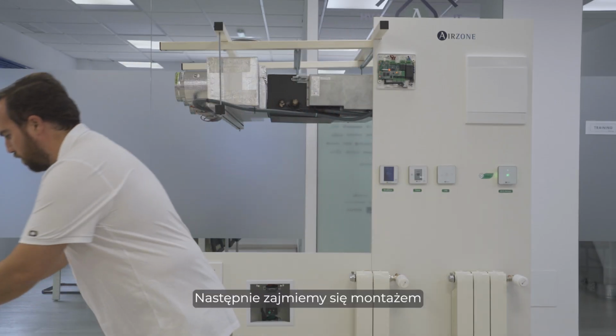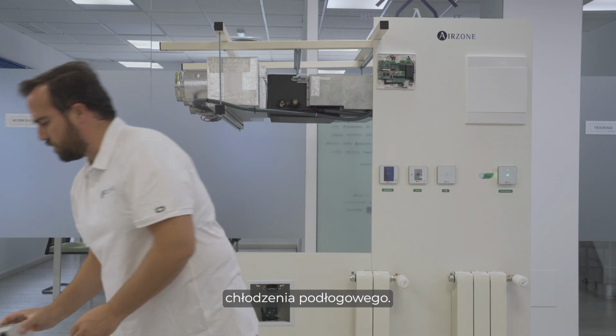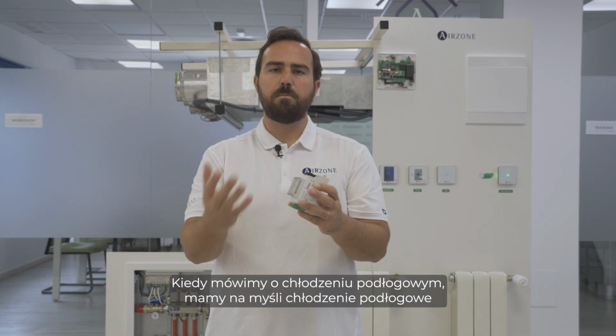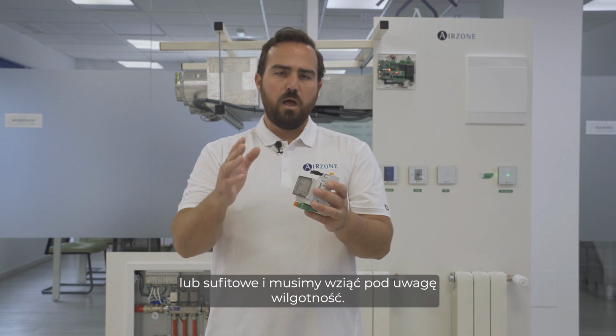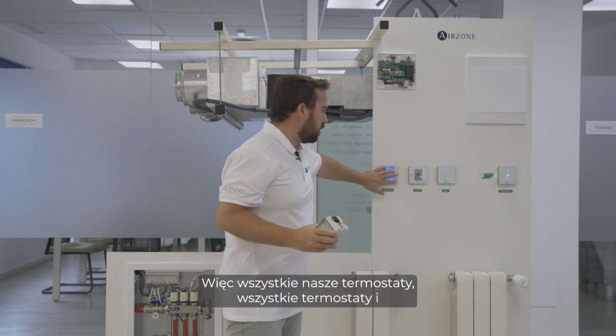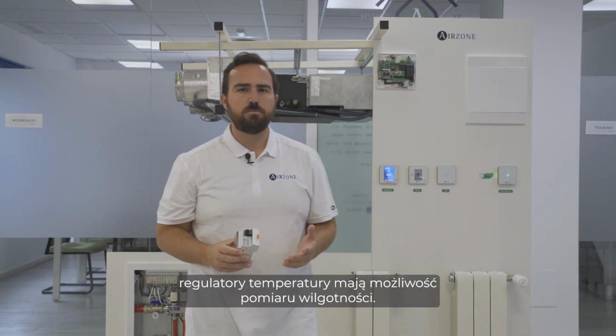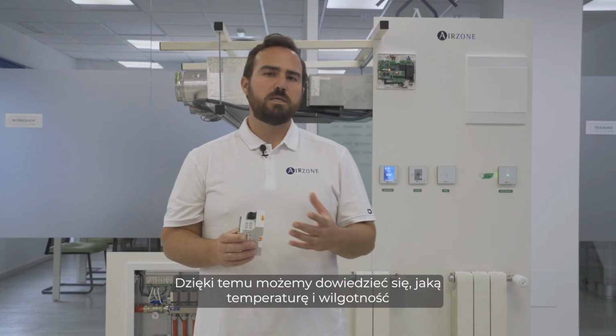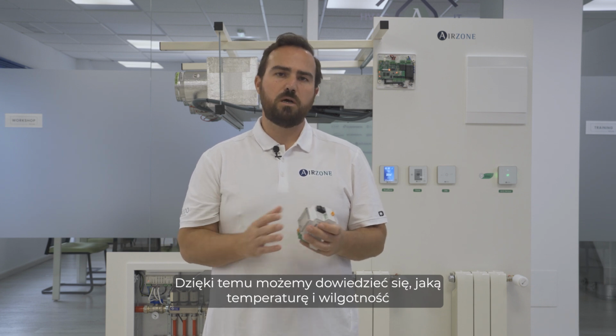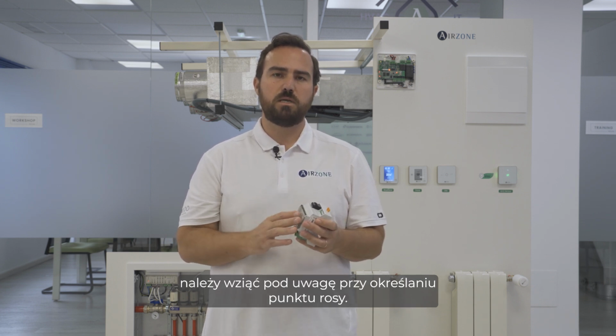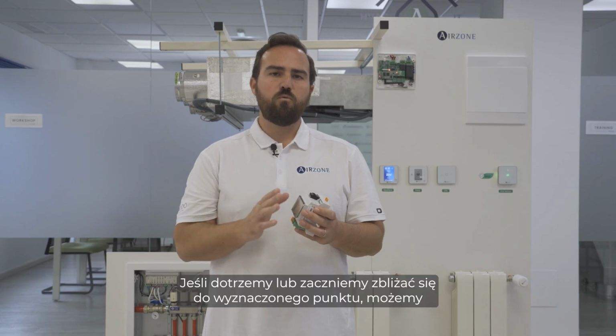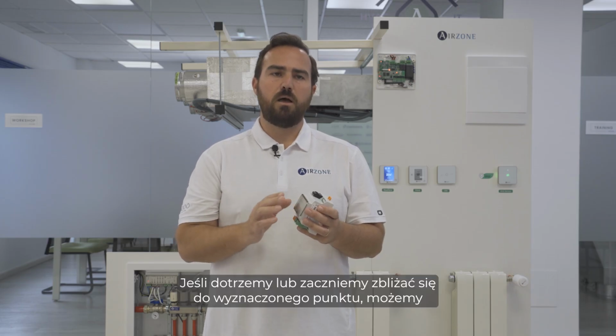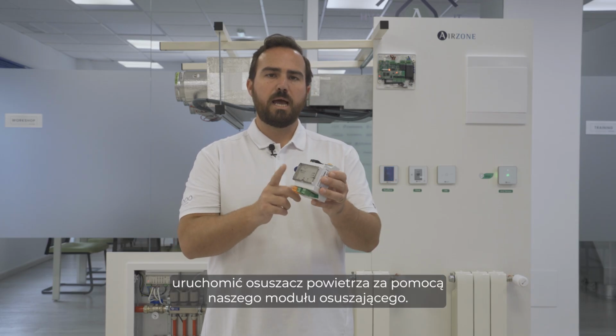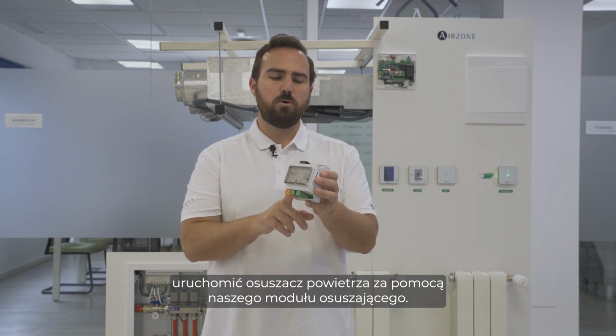Then for the installation of underfloor cooling, which can be underfloor cooling or ceiling cooling, we need to take into consideration humidity. All of our Airzone thermostats have the possibility of reading humidity, so this allows us to know what temperature and humidity percentage we need to consider for the dew point. If we reach or start reaching that designated point, we can activate a dehumidifier through our dry module.